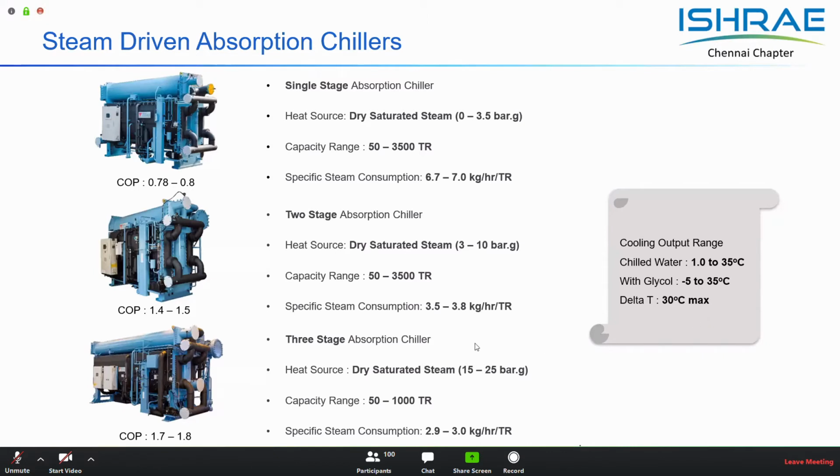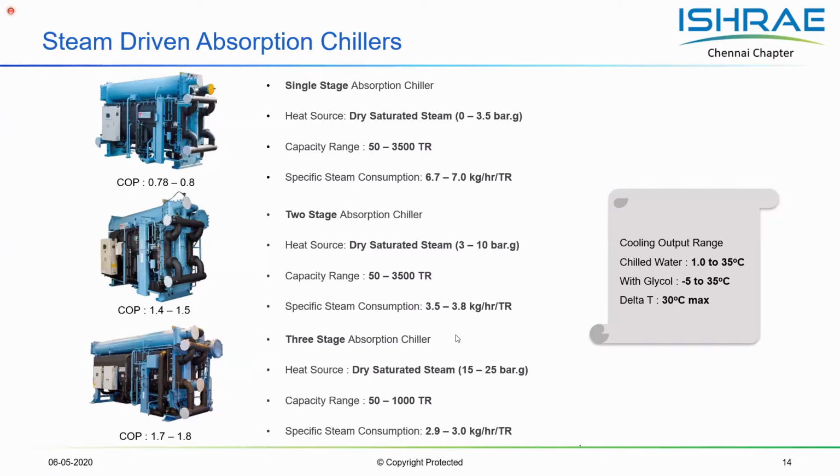This is using the conventional lithium bromide absorption unit. Certain applications would demand a high delta T in the chilled water, something like ambient water getting cooled to 7 or 5 or lower temperatures. Absorption technology can handle temperature differences in chilled water as high as 30 degrees Celsius. So ambient water to 5 degrees Celsius is also possible.